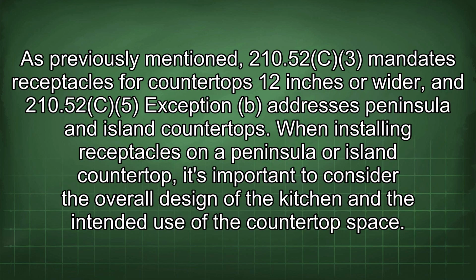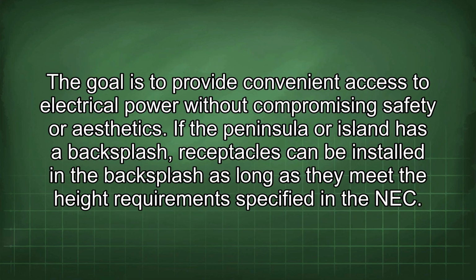As previously mentioned, 210.52C3 mandates receptacles for countertops 12 inches or wider, and 210.52C5 Exception B addresses peninsula and island countertops. When installing receptacles on a peninsula or island countertop, it's important to consider the overall design of the kitchen and the intended use of the countertop space. The goal is to provide convenient access to electrical power without compromising safety or aesthetics.